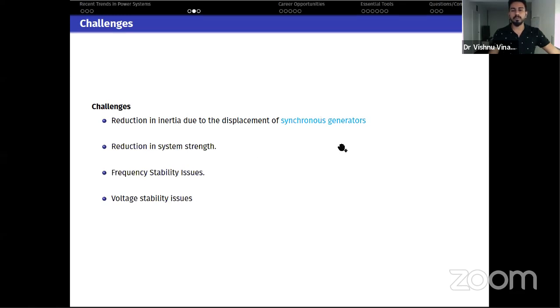So if we replace synchronous machines with PV and wind sources, these sources are typically power electronic based sources. So the amount of current that can be supplied using these power electronic switches is very limited, and it obviously cannot give a 200% leverage. It can go up to a maximum of 1.2 or 1.3 times its rated current. So basically, if we replace a 500 megawatt generator in a system with a 500 megawatt PV, we are losing a significant amount of inertia from the network and a significant amount of system strength. So this will cause frequency instability in the network, and this will cause voltage instability in the network.